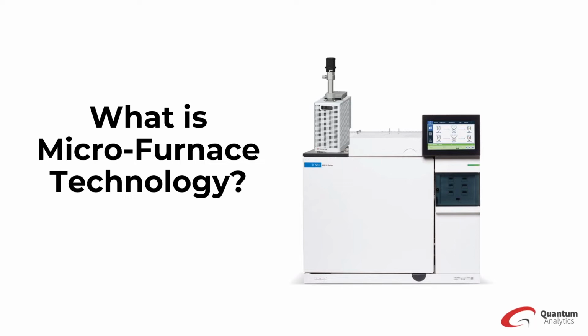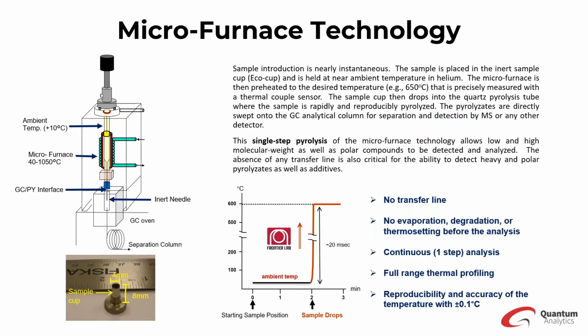In traditional GC, we're really limited to volatile or semi-volatile compounds that are conducive to the GC inlet temperatures. However, with a furnace, we're able to characterize larger molecular weight compounds, including polymeric compounds, such as in microplastics. So here's a little cross-section of your microfurnace. This furnace houses a quartz tube. This is where the sample cup is dropped into to be pyrolyzed by the furnace.